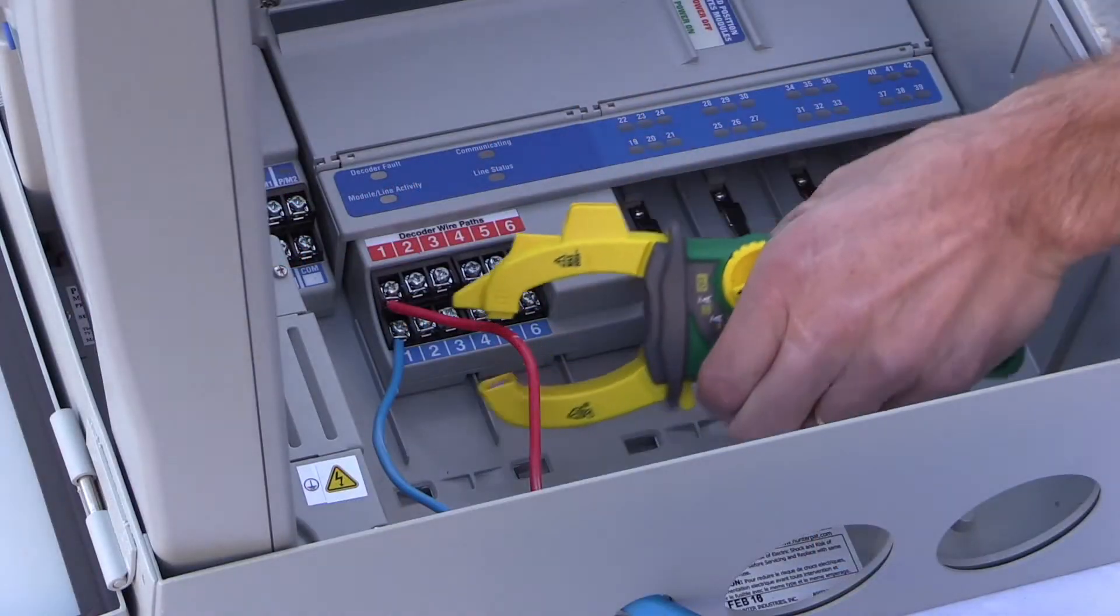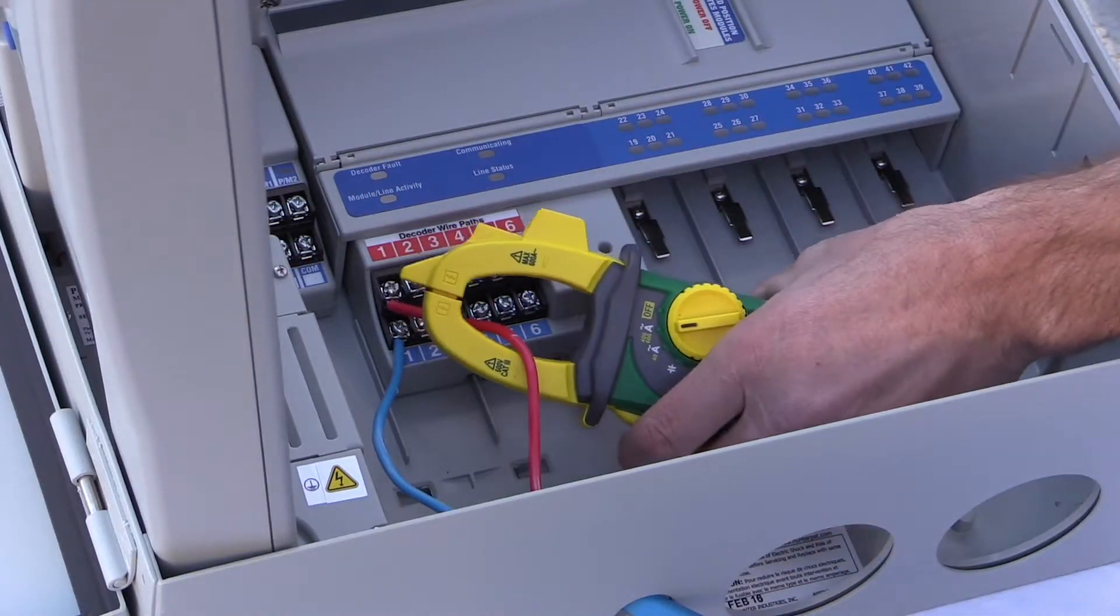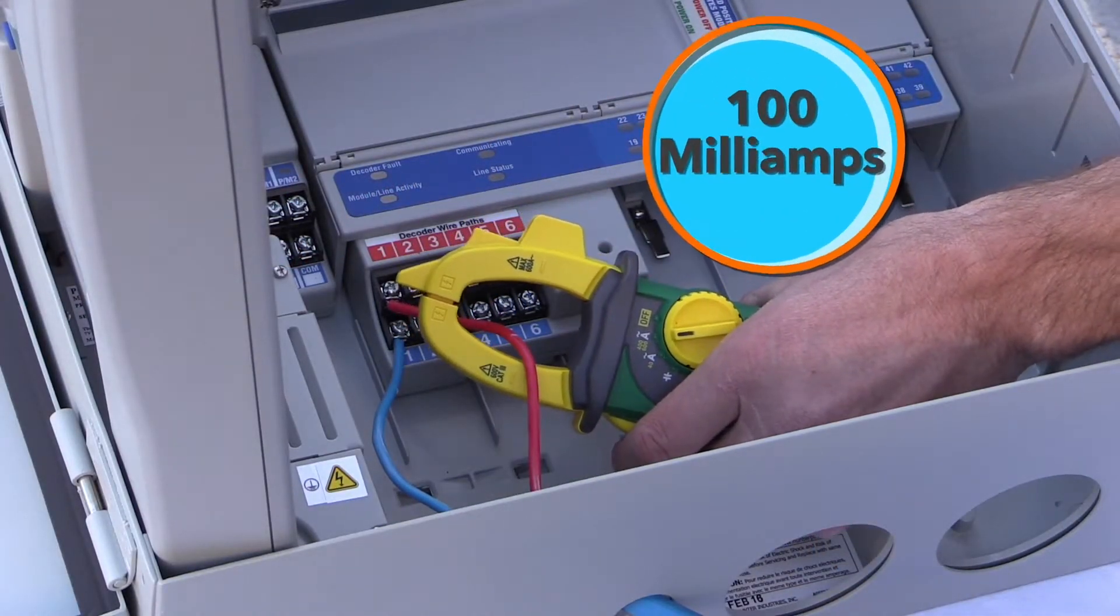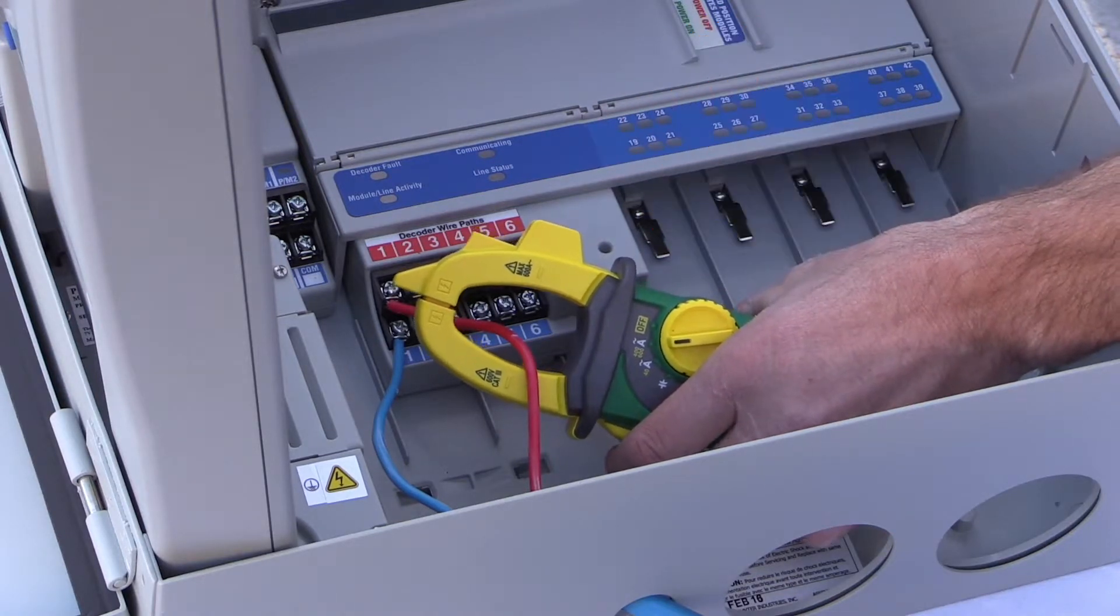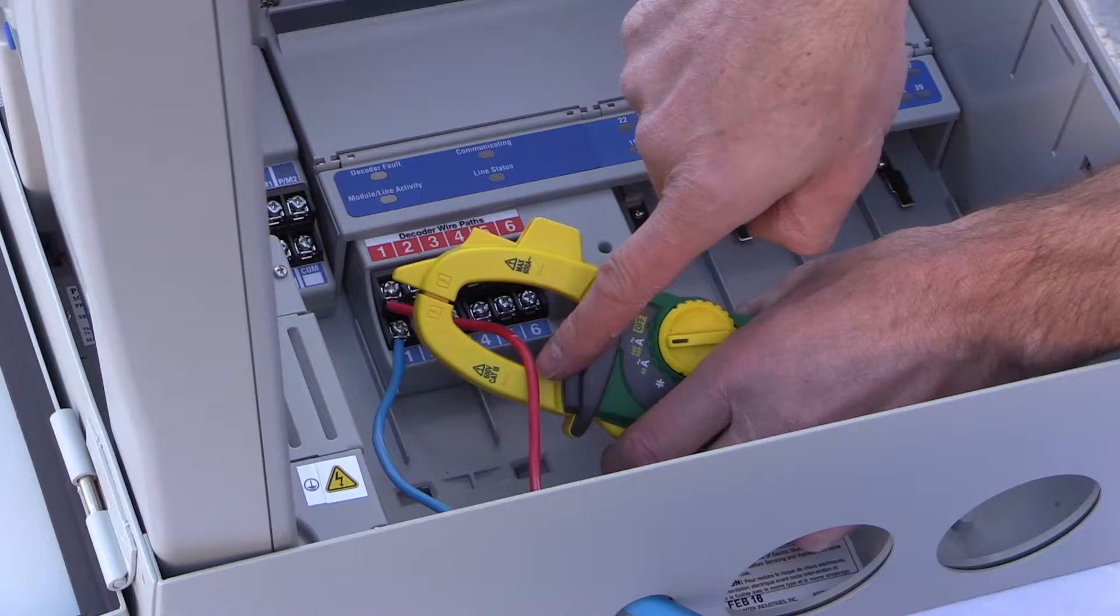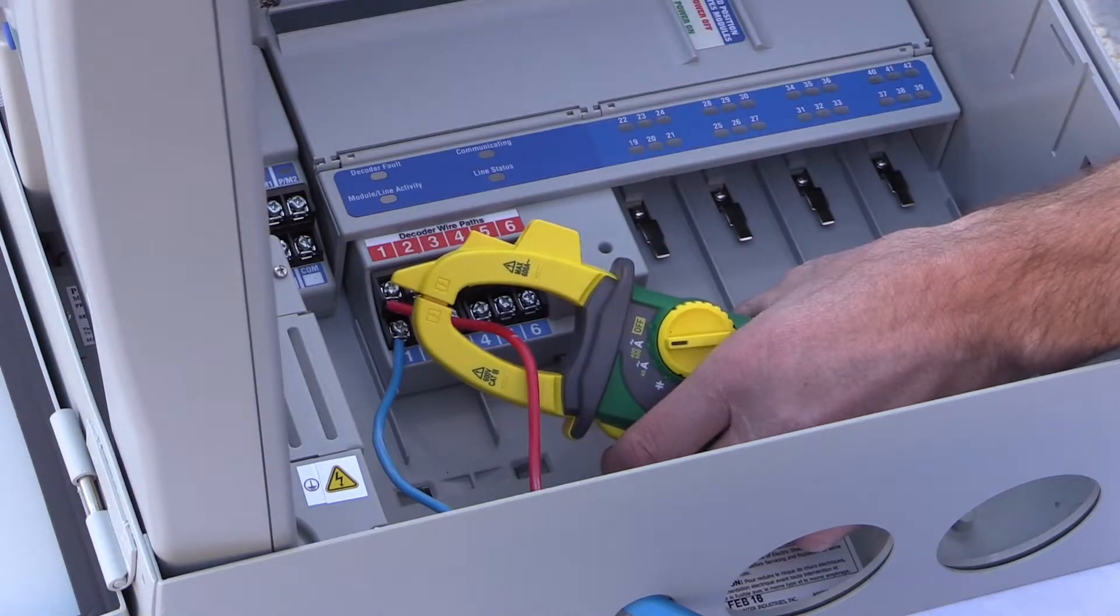If we clamp the meter around one wire at the start of the path, we should get a current flow reading of 100 mA with no solenoids activated. Be sure to place only one wire, the outbound wire, in the clamp to get an accurate reading.